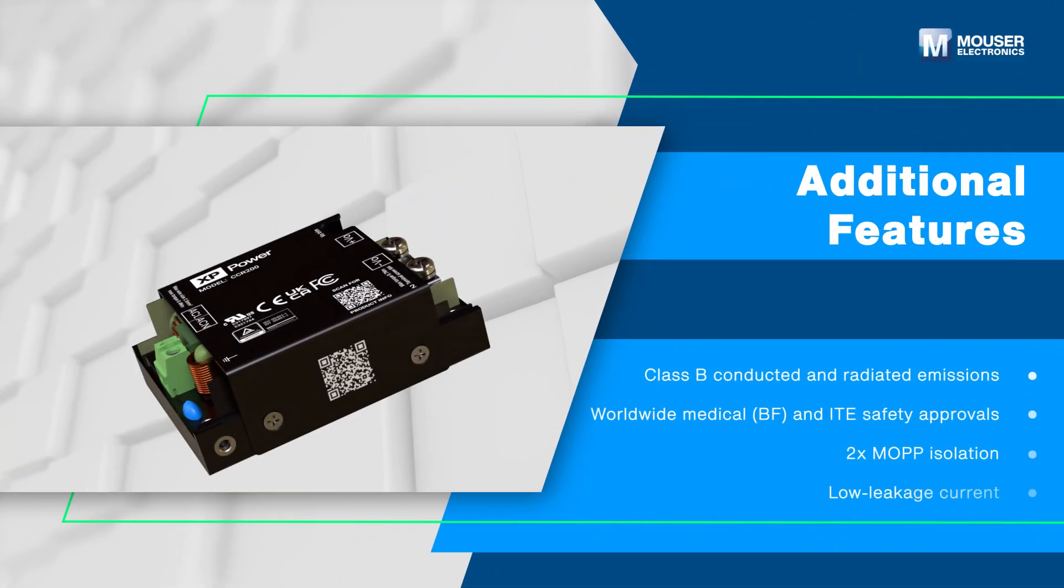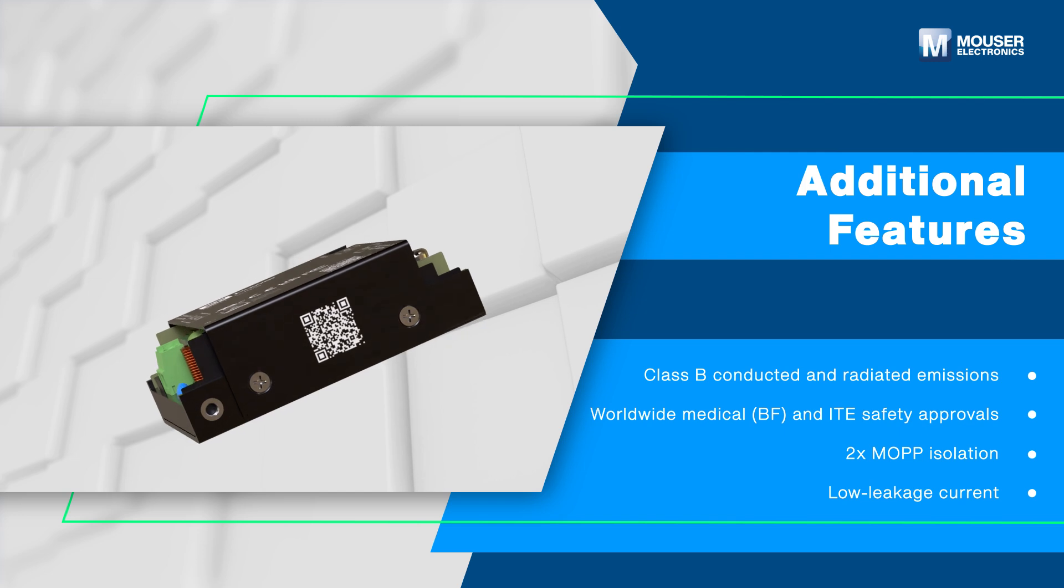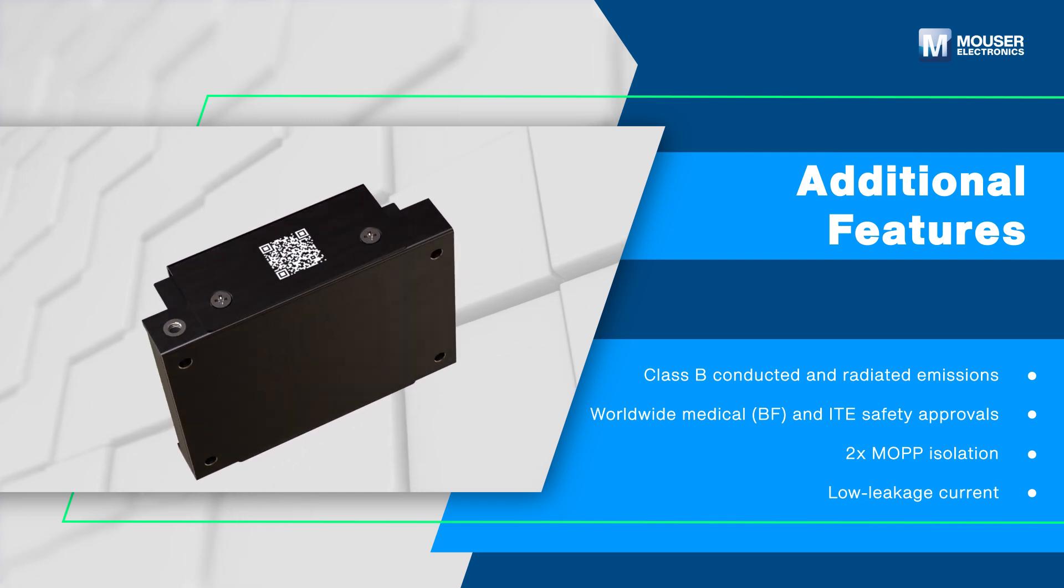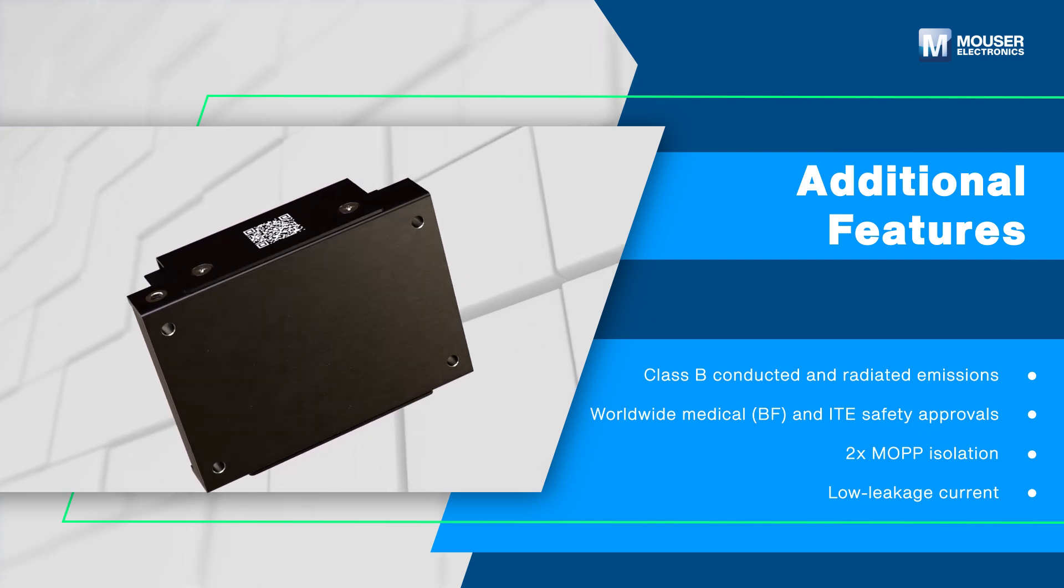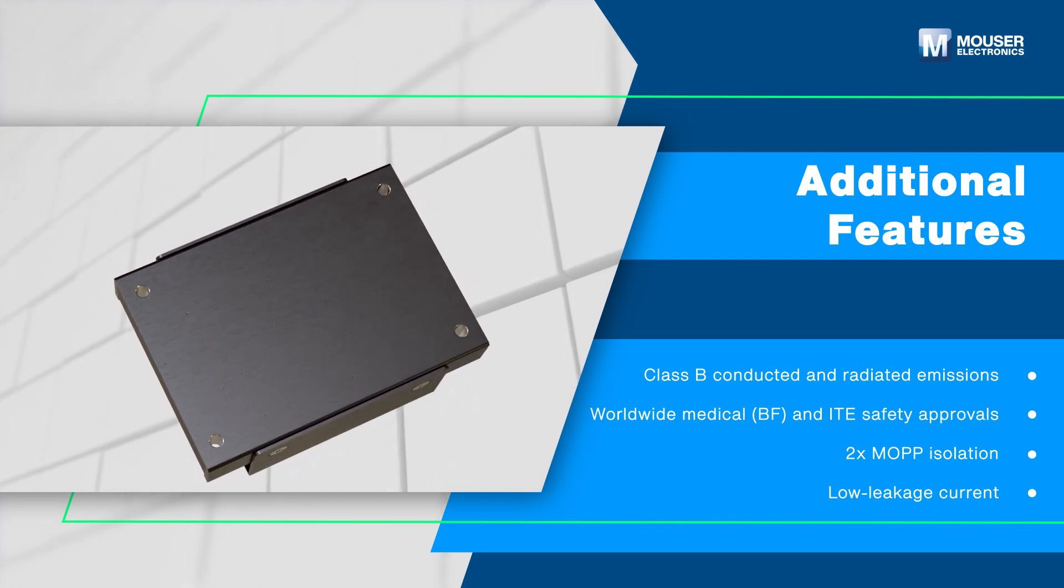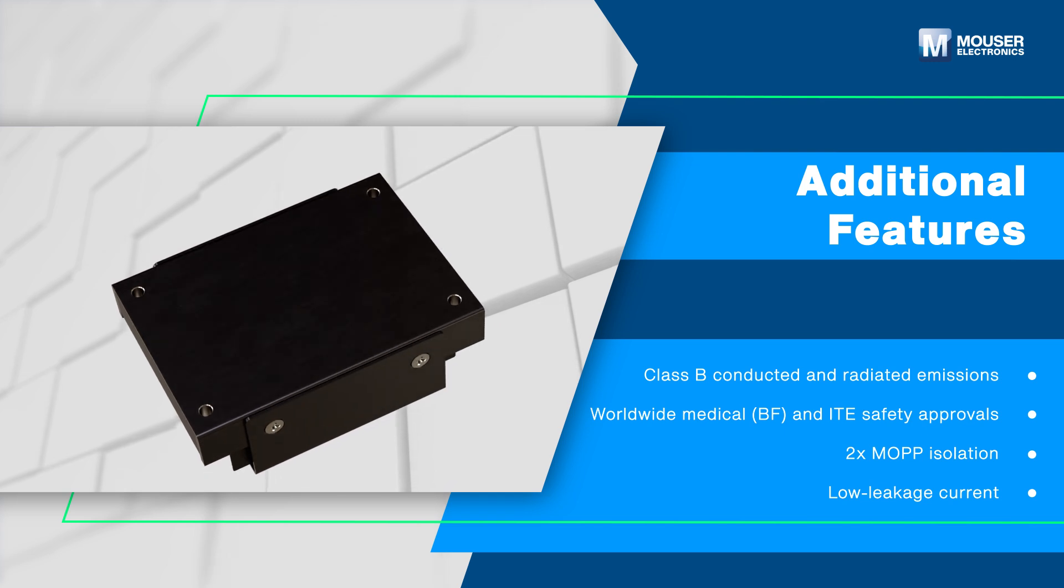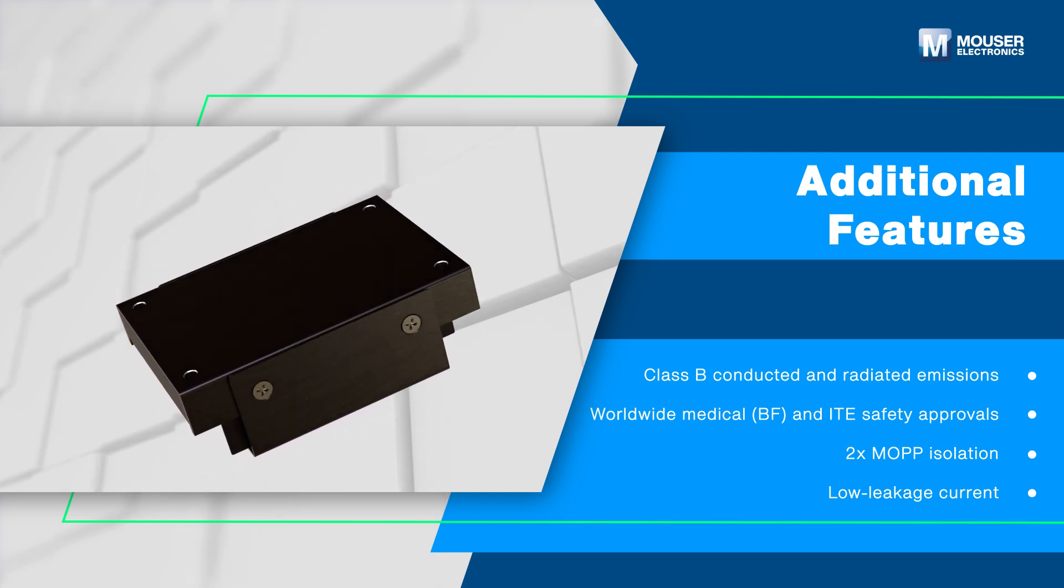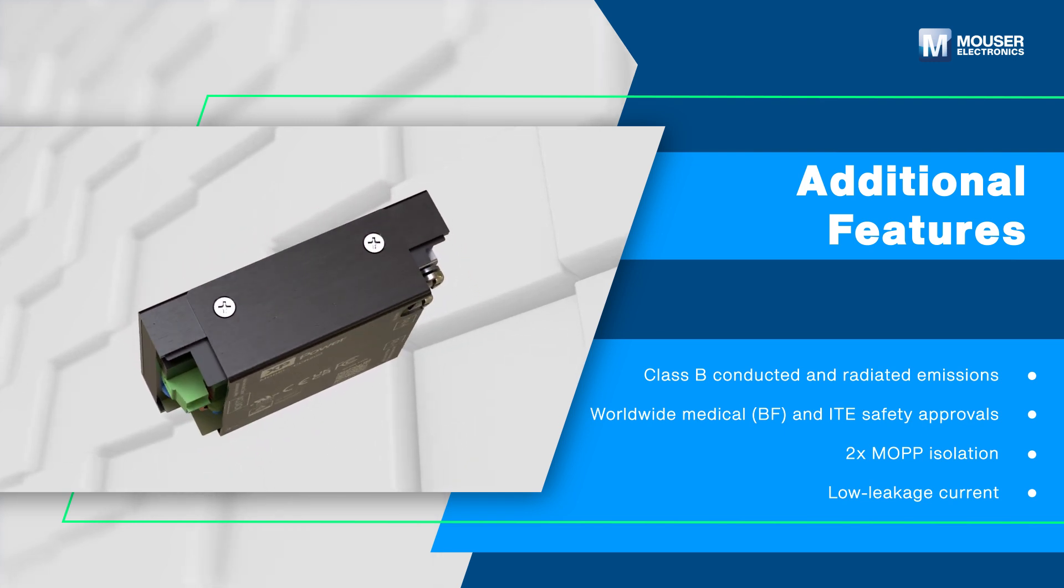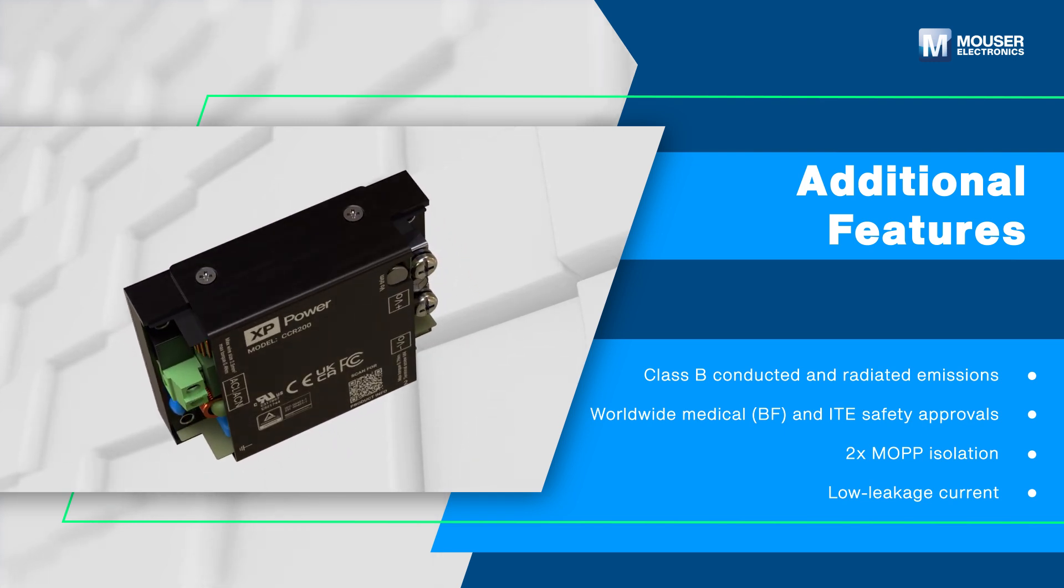Additionally, the CCR series features class B conducted and radiated emissions, worldwide industrial and medical or BF safety approvals, 2 times MOPP isolation, and low leakage current for enhanced safety and performance.